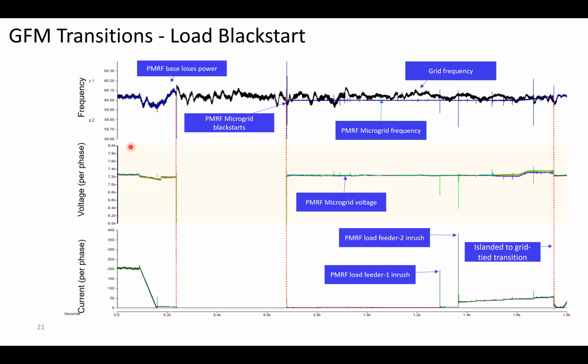So that's frequency versus time, voltage per phase, and current per phase. So this is the AES plant grid tied. We open the islanding breaker, shut down the plant, so the PMRF base loses power. And we start the load Blackstart sequence somewhere around here. It takes us about 5 to 10 minutes to start up the AES plant. We Blackstart, the PMRF Microgrid Blackstarts, so the AES plant Blackstarts and forms the frequency for the microgrid.